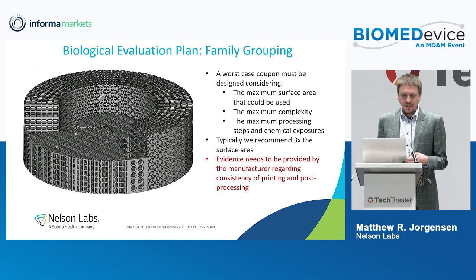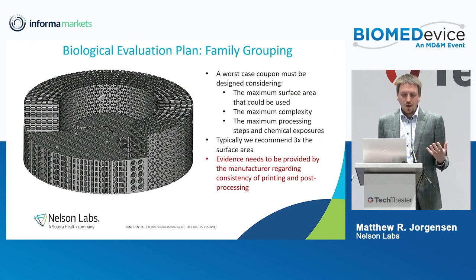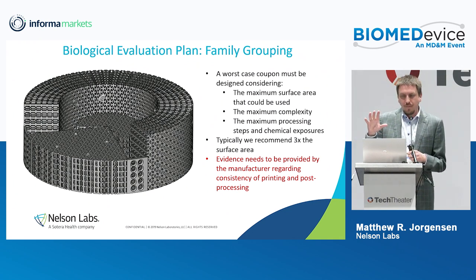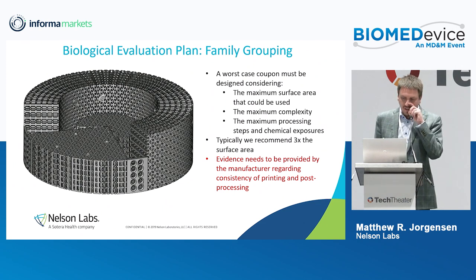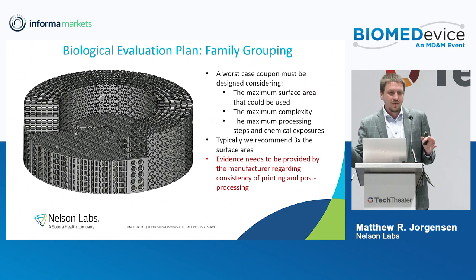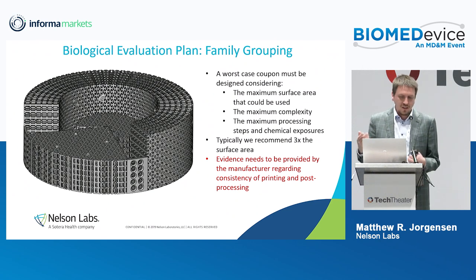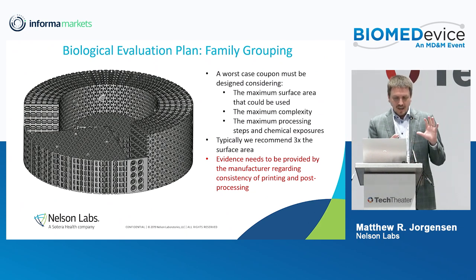When one of these devices comes to us, the first question is always: what are we actually going to test? We know how it should be categorized — permanent tissue bone contacting — but every device is different, so it's hard to know which thing is really going to be representative. The first step is always designing a worst case construct that's going to be more challenging to pass from the perspective of biocompatibility than any one of these that will ever be printed in actual use. For example, we said the real device would only ever have a certain surface area, so we take two times that surface area, and look at the number of narrow holes that could be difficult to clean, and design one of these to be the worst case thing to test.